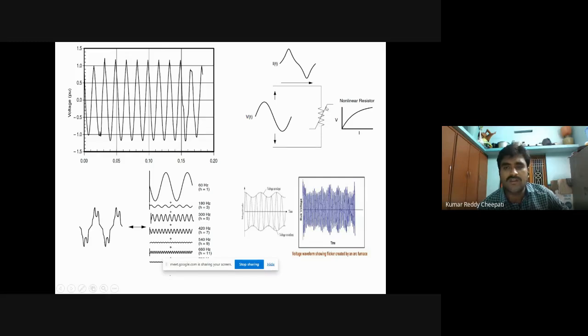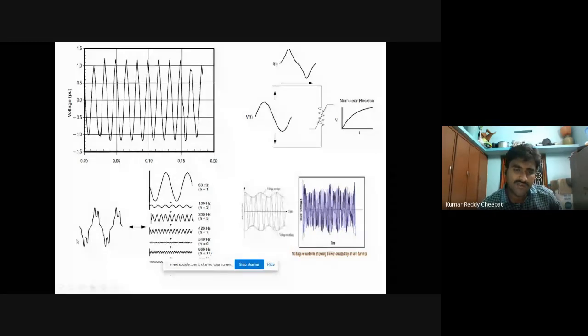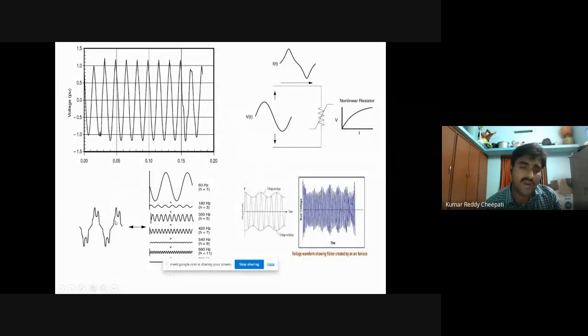Because of connecting a nonlinear load, it draws a non-sinusoidal current. Non-sinusoidal current means it is a totally non-sinusoidal waveform and distorted in nature. For example, this is the distorted current waveform. In this distorted current waveform, we have the current harmonics along with the fundamental frequency. As you can see here, if you split this distorted waveform using Fourier series, you can find many harmonic components along with the fundamental frequency. So we have the fundamental frequency of 60 hertz or 50 hertz. Along with that, we have the third harmonic, fifth harmonic, seventh harmonic, ninth harmonic, 11th harmonic, and so on.